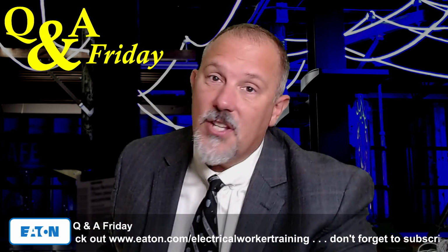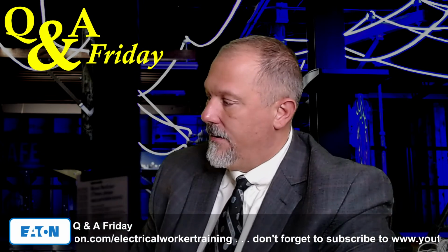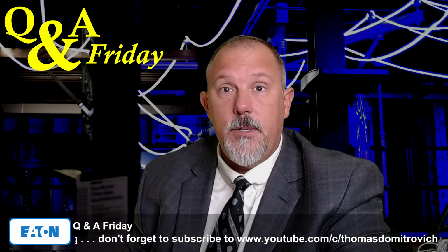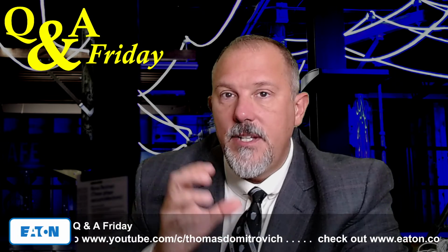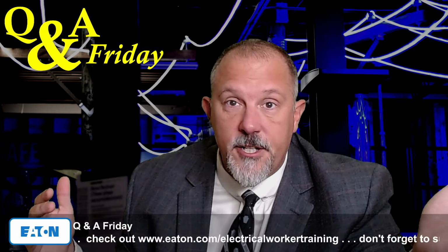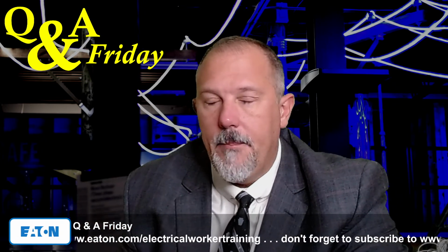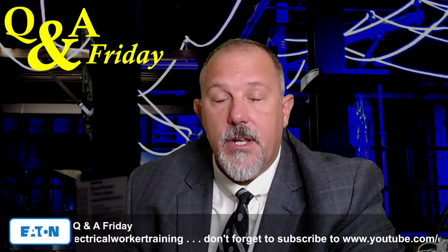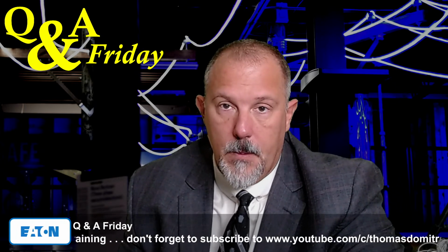If you think about when you have a series rated system, and we just talked about this last, maybe Tuesday? I think it was Tuesday. We talked about short circuit current ratings and series ratings, the motor contribution. So if you have a series rated system and your available fault current is high enough that it's basically in the instantaneous region of your upstream and your downstream device, what does that mean? Why do I know that? Because my bolted fault current value is so high that my upstream and my downstream device are both going to clear the fault.